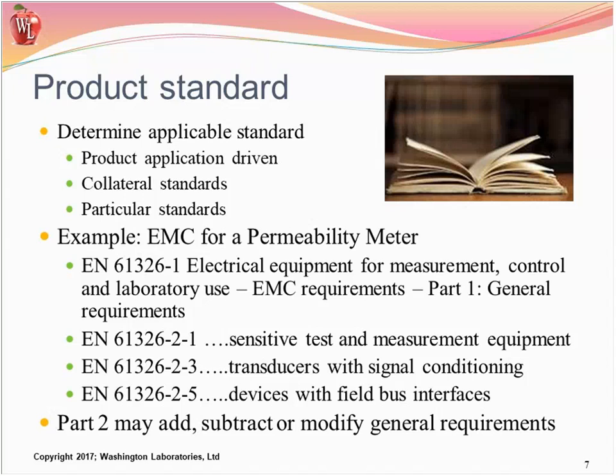So the Part 2 standard may add, subtract, or modify general requirements. For instance, in the sensitive measurement equipment for magnetic field, the general standard says it must be immune to a certain level of magnetic field, and then the -2-1 says no, you can't do that because it's going to be sensitive—it can't comply if you apply that Part 1 standard. So it modifies the requirement for magnetic field immunity and may do other things as well.